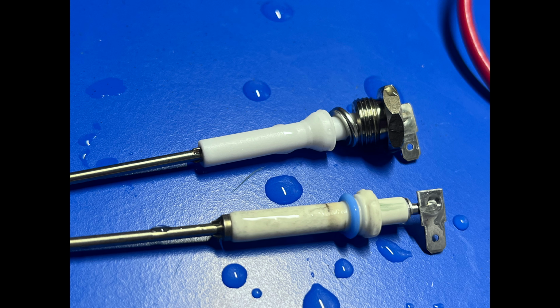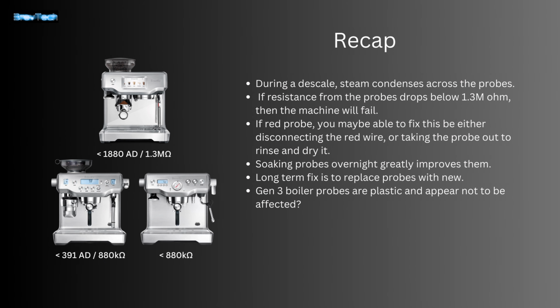Let's recap on what we've found so far. We know that during a descale the hot water is emptied out and the steam condenses across the probes. We also know that on the Oracle Touch I have here, if that steam causes the resistance from the probes to ground to drop below 1.3 megaohms, then the machine will, depending on which probe is affected, either turn off the pump too early and/or turn on the heat when there's no water in the boiler.